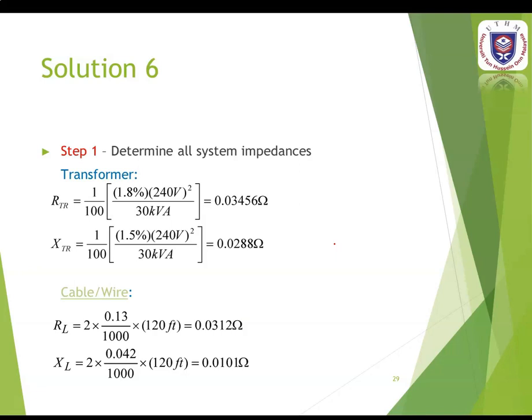For the transformer, you can use the equation: resistance or reactance equals 1 over 100 times the percentage of resistance or reactance of the transformer, times the secondary line voltage squared, divided by the apparent power. For the resistance of the transformer you get 0.03456 ohms, while for the reactance of the transformer you get 0.0288 ohms.